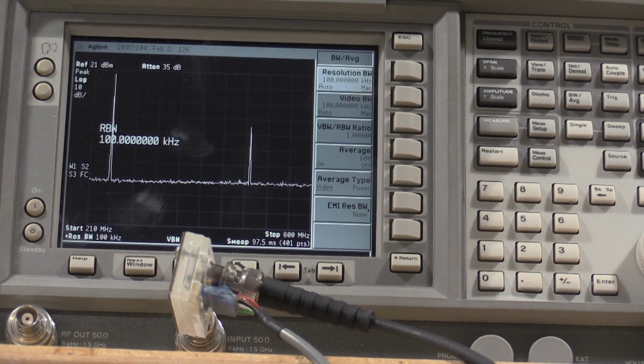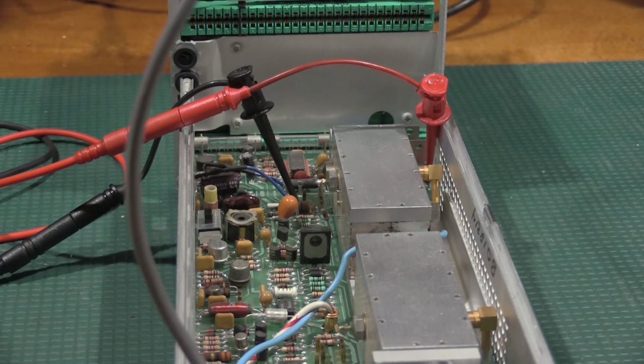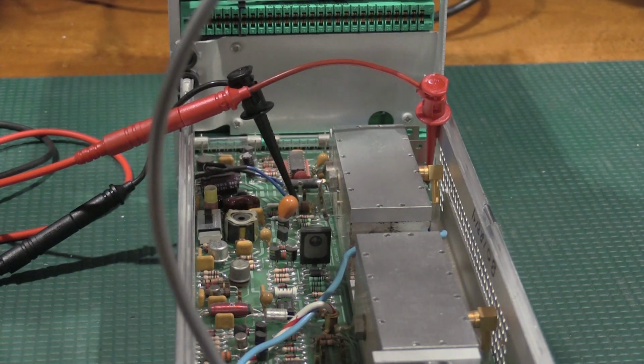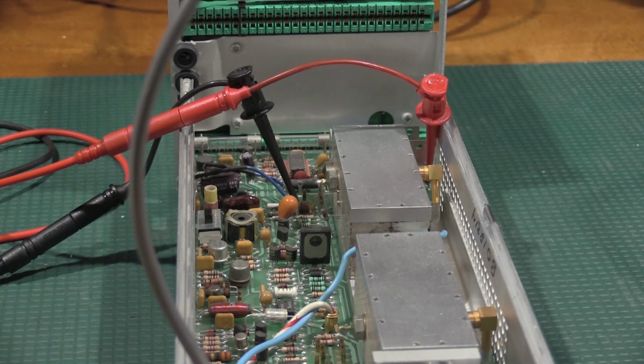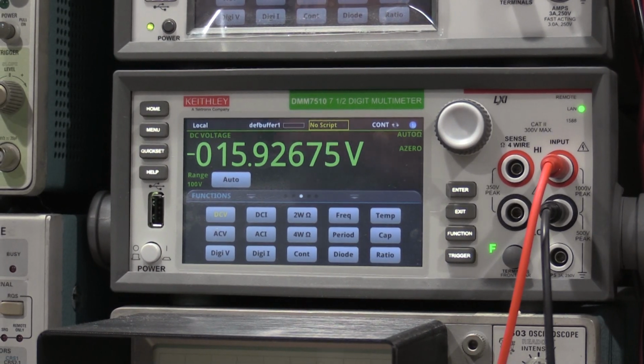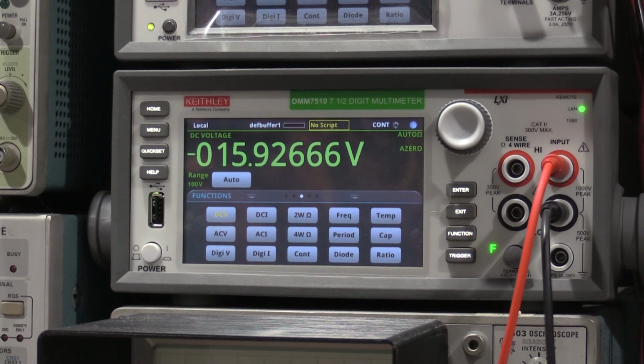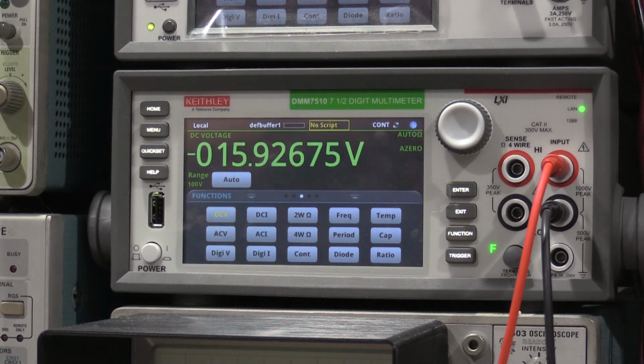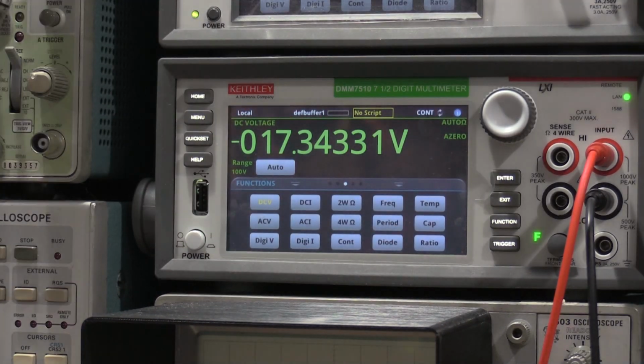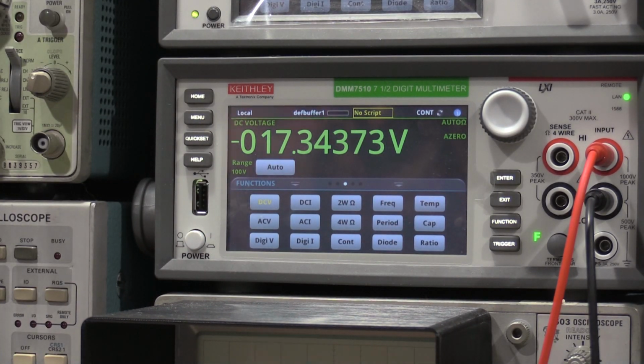It tells you to set up the spectrum analyzer. You don't do anything with it in this step, which is bizarre, but that's what they wanted you to do. The important parts of this step are on the voltmeter. So we have ground on the ground test point, and then the buffer current test point for a reading of negative 15.9. We have our reading of 15.9, and now we have to move the positive lead to test point 2. And we need to check capacitor C125, and we're looking for a balance.